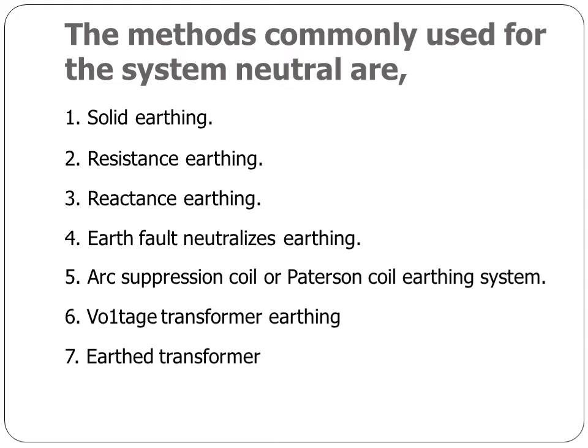The methods commonly used for the system neutral are: first one is solid earthing, second one is resistance earthing, third one is reactance earthing, fourth is earth fault neutralizer earthing, arc suppression coil or Peterson coil earthing, voltage transformer earthing and earthed transformers. These are the methods commonly used.